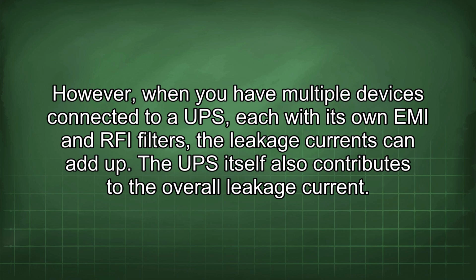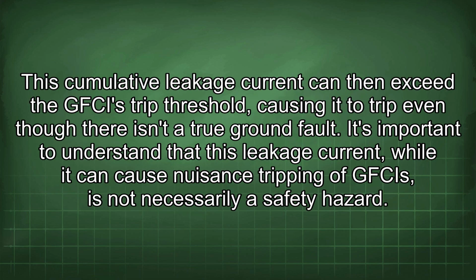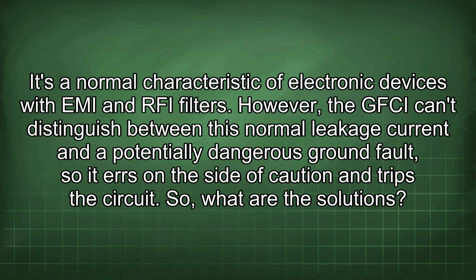The UPS itself also contributes to the overall leakage current. This cumulative leakage current can then exceed the GFCI's trip threshold, causing it to trip even though there isn't a true ground fault. It's important to understand that this leakage current, while it can cause nuisance tripping of GFCIs, is not necessarily a safety hazard. It's a normal characteristic of electronic devices with EMI and RFI filters. However, the GFCI can't distinguish between this normal leakage current and a potentially dangerous ground fault, so it errs on the side of caution and trips the circuit.